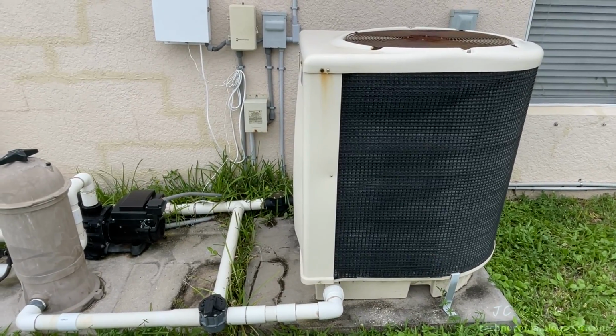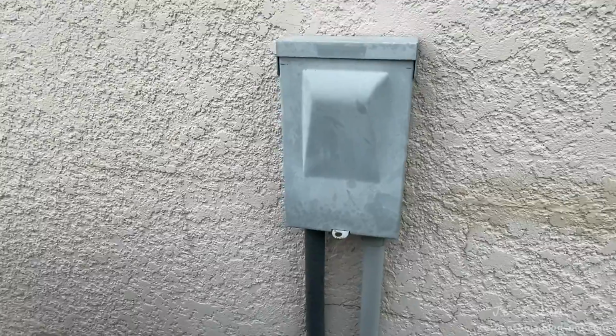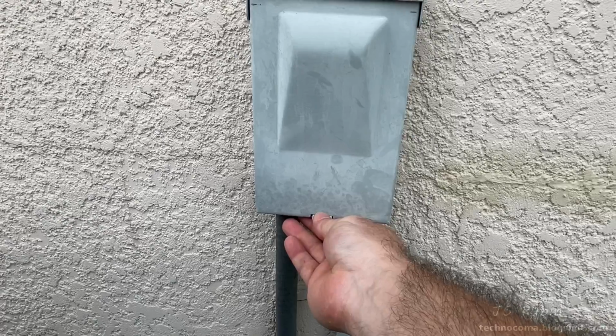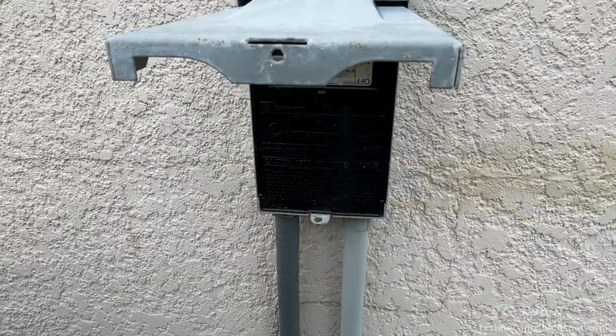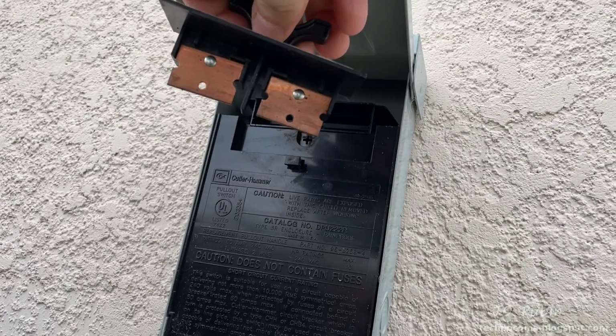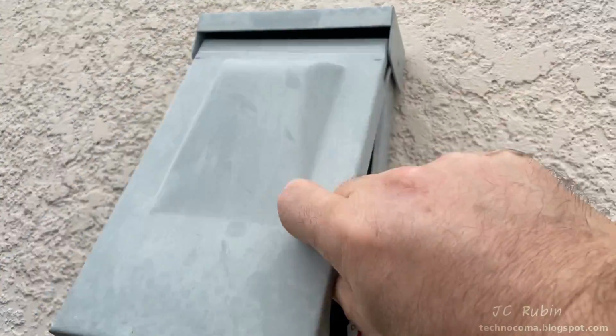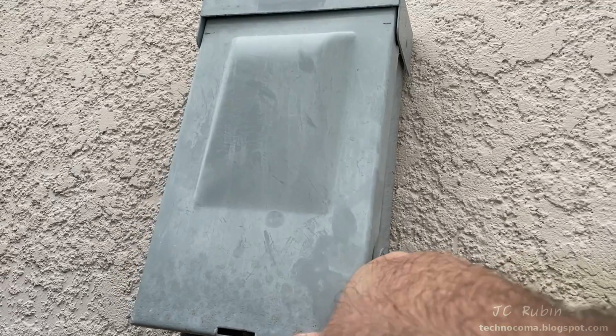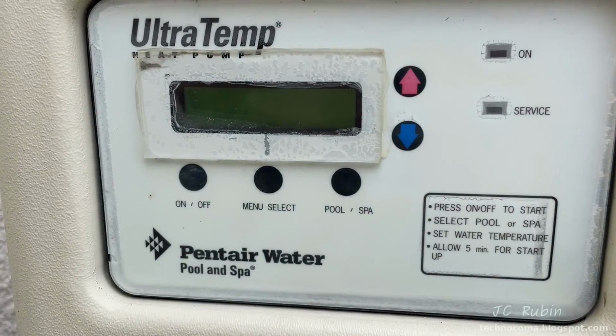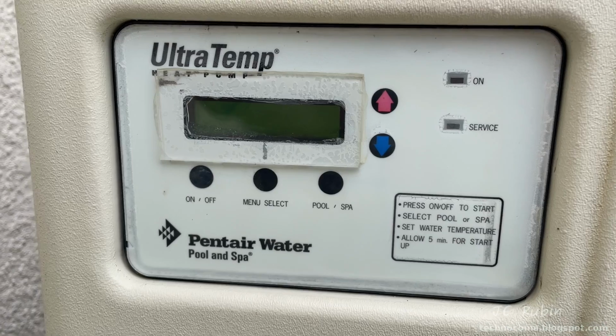I trace the power right back up to this panel. My panel doesn't have a fuse or a switch, it's a disconnect, so I pull it right out, and I'm going to store this with the other parts away from this panel. I could reinstall it upside down, I simply choose not to. The display is off and there is no more power going to the unit.